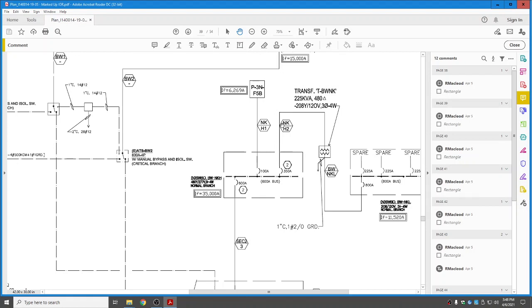Okay, we're also coming up, we have another conduit size and wire size that goes over and feeds to a transformer. Transformer T, BWNK, 225 kVA, 480, 208. Okay, and it's going to step that power down from the 480 to the 208 120 volt, 3-phase, 4-wire. Coming out down at the bottom, you'll see we have a 1-inch conduit with a number 2-aught ground to ground that transformer, possibly to the building steel.